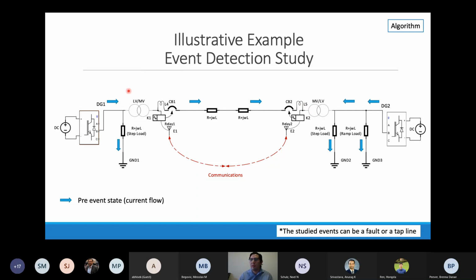The blue lines present the pre-state of any event and how the current is flowing. So we know that this inverter is feeding this load, is feeding the distribution line, and is also feeding this load, and the other inverter is feeding this load and this load. So this is how we are sharing the load here. But now we will test what happens when a fault happens. Here I'm showing a fault in this portion of the line.